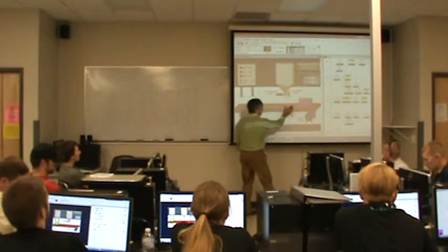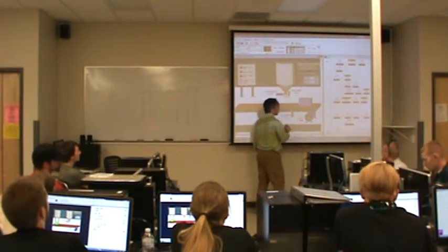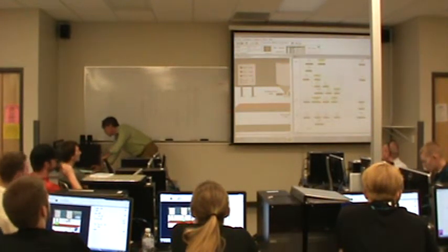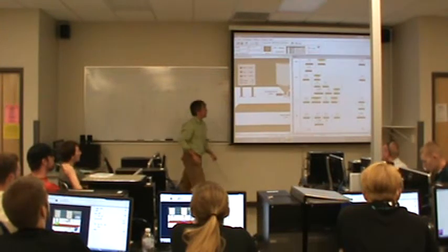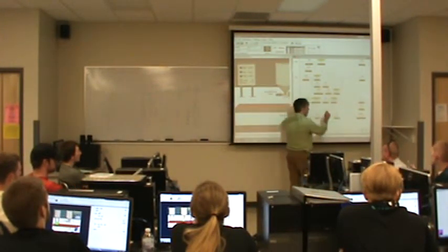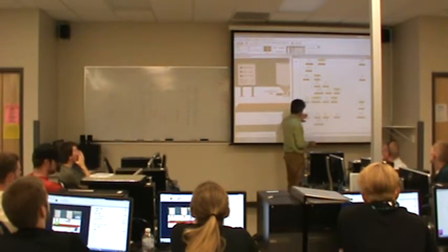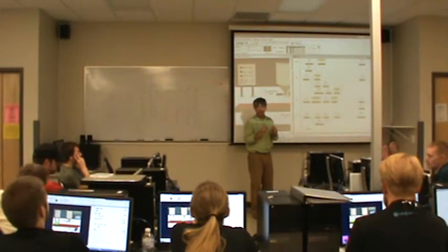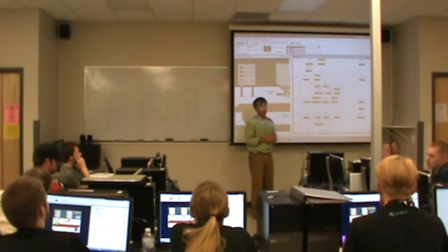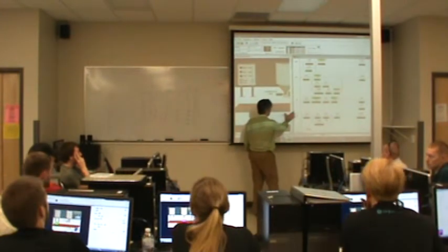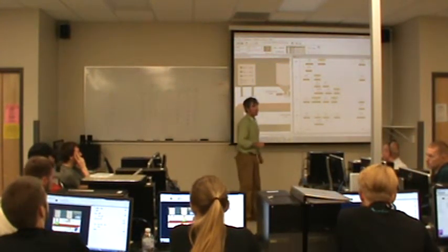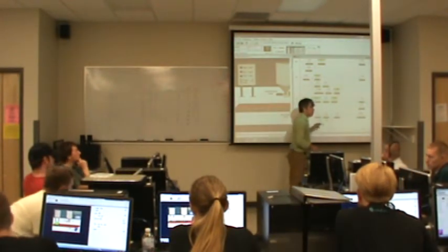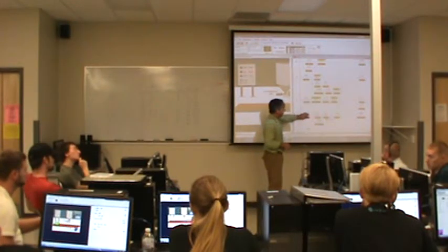If I can stop it right here where prox is true and level is not true, consider what happens to the bit. If I stop it at that point, because I've got this run lamp in there, the system is going to forget that it had a full box because this shutting off will also break the seal-in. If that happens and then I start it up again, the system is going to pour product all over the floor again because it's going to see a box in position by prox that is not full by level. And so it's going to start the flow up again because it does not remember that there was a full box. So in my coding, I would actually recommend that we remove this.